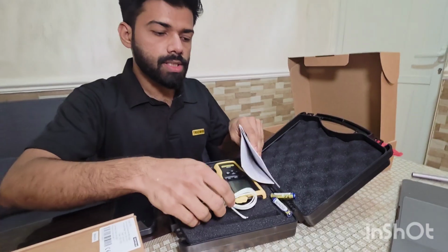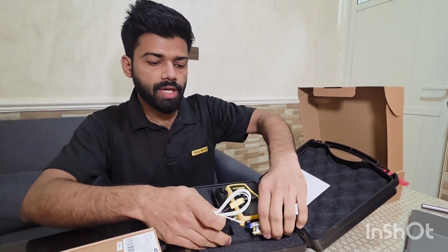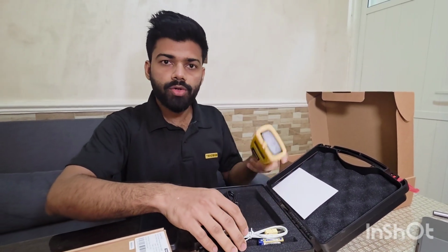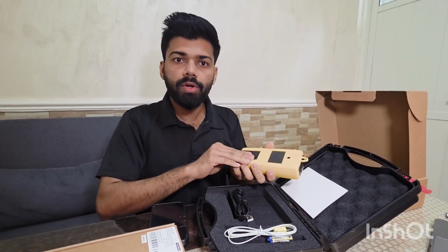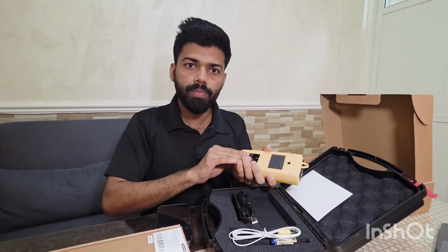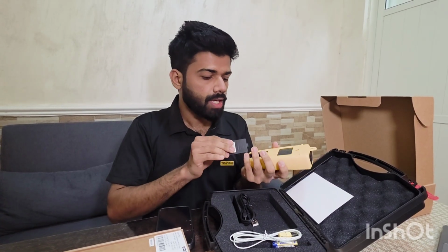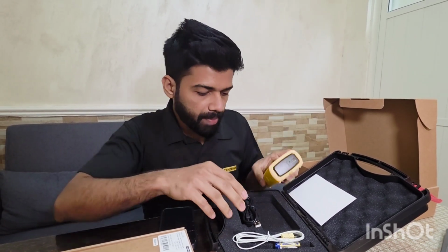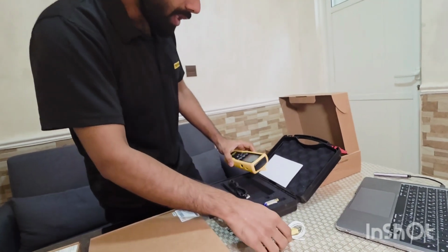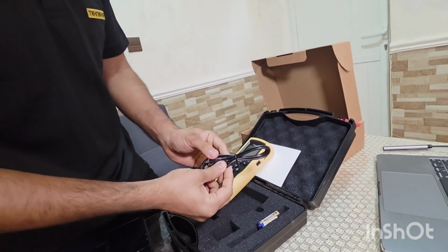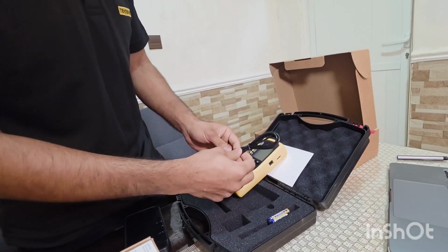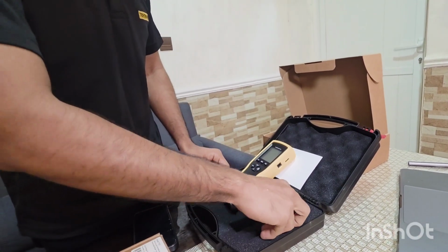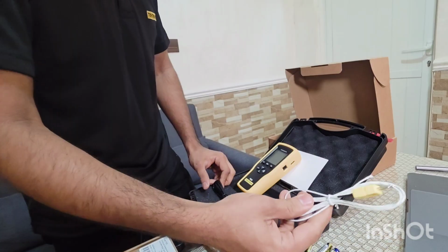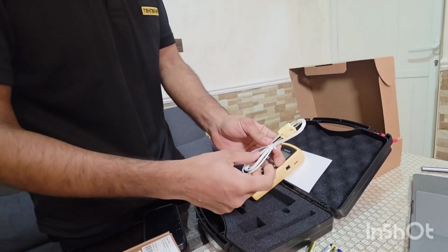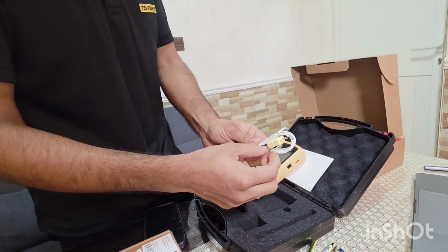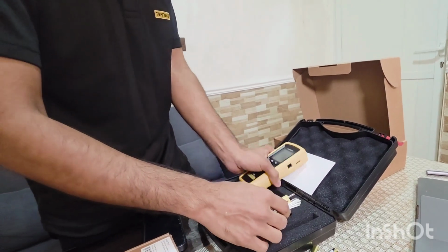Everyone knows the thermocouple works on the basic principle of the Seebeck effect. When two dissimilar metals are joined together and kept at two different temperatures, EMF will be induced in it, and that EMF is directly proportional to the temperature applied. And here in the package you can see for the T510, this is a logger. This is a USB cable to interface with the computer for retrieving the logged data, and batteries are included, and one type K bead wire probe is included, and this probe is capable of measuring from -50 to 200 degrees Celsius.